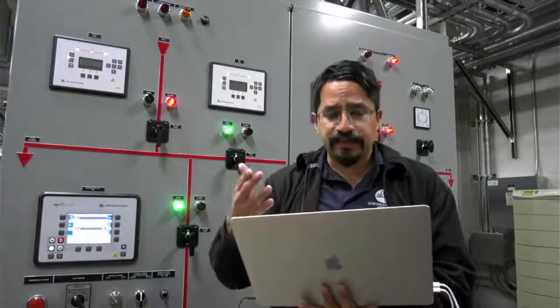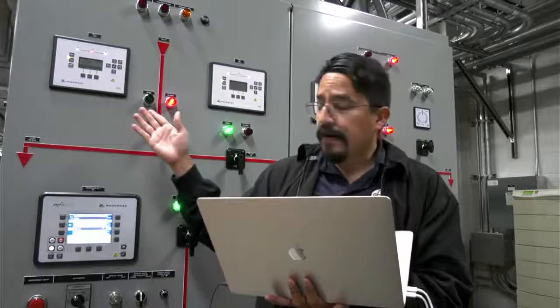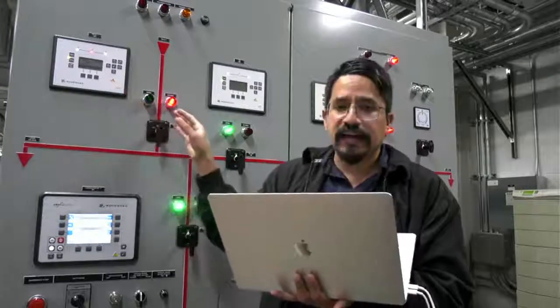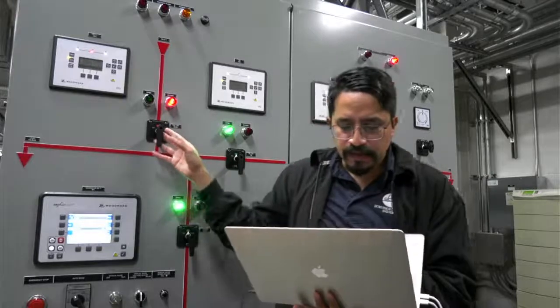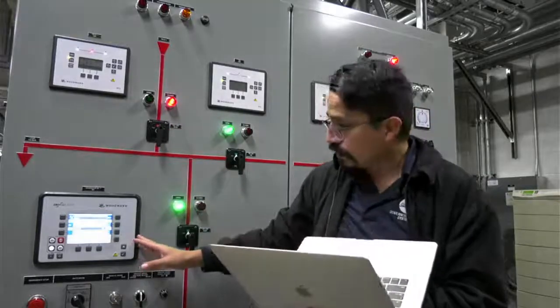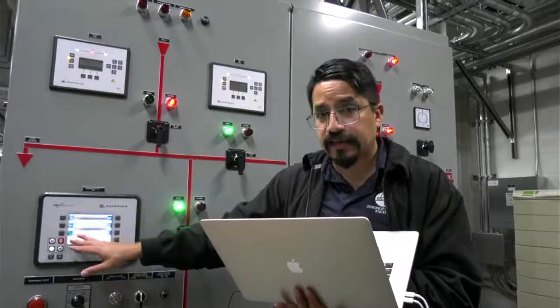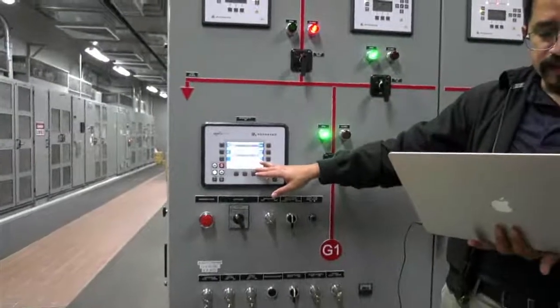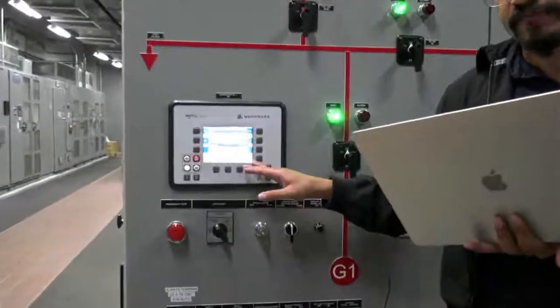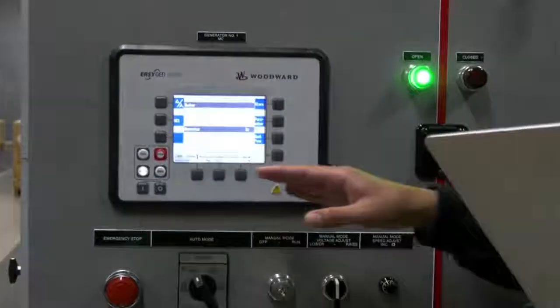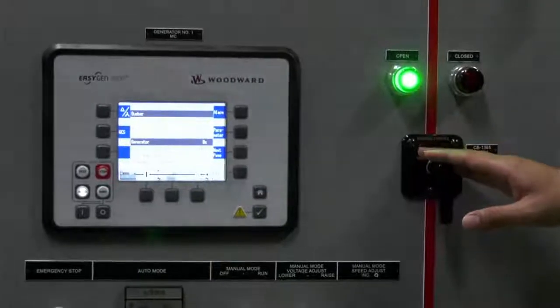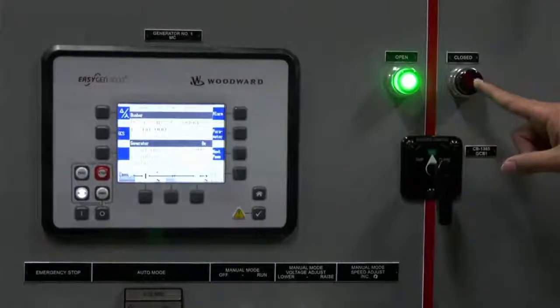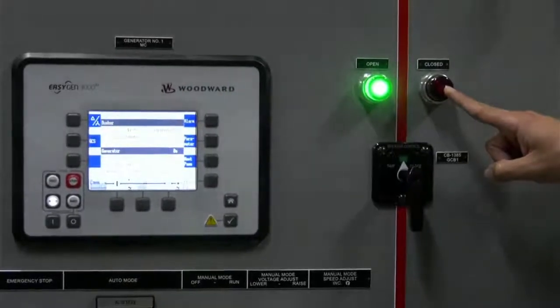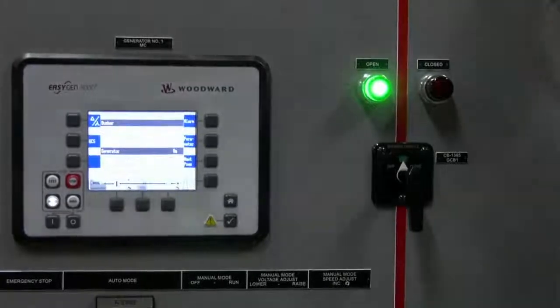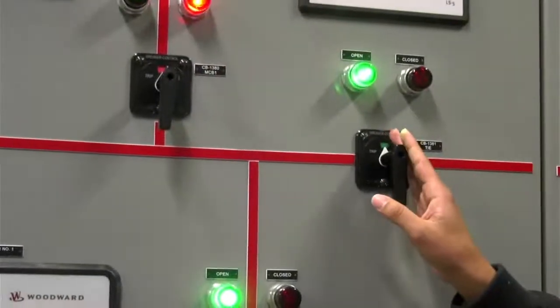So if the time expires, we are gonna open the LS5. They open the circuit breakers, both of them. The generator is gonna start. So here on the screen, you're gonna see the generator is starting. Right, the generator will go to rated speed and rated voltage. Once the generator is stable, it's gonna close the circuit breaker. So you're gonna see this pilot light red, right? And the tiebreaker is gonna be opened. You have the option to close it, but in a normal condition, this is gonna be open.